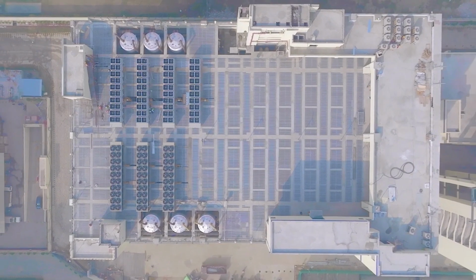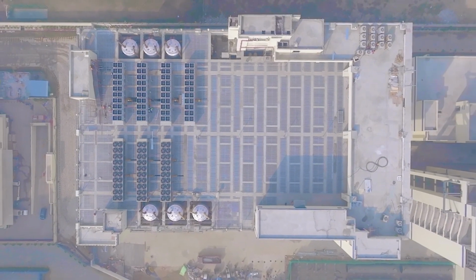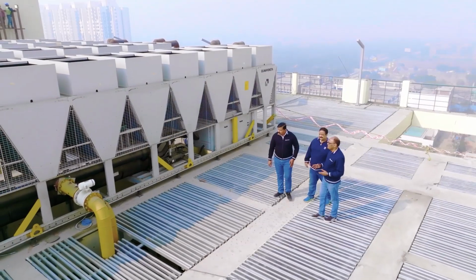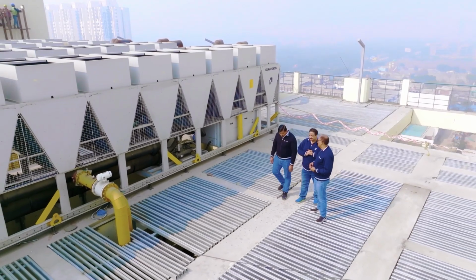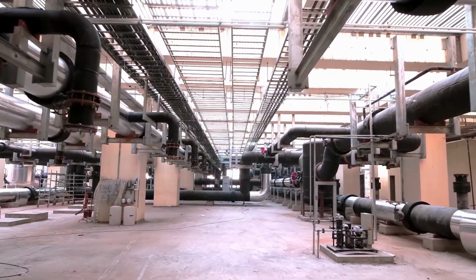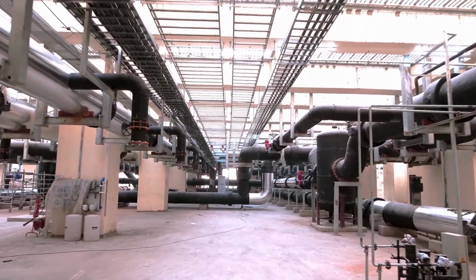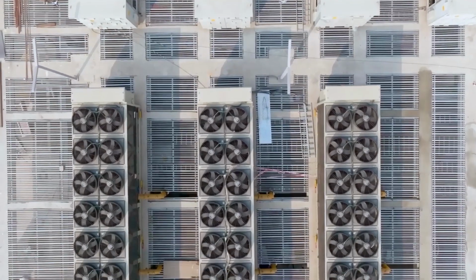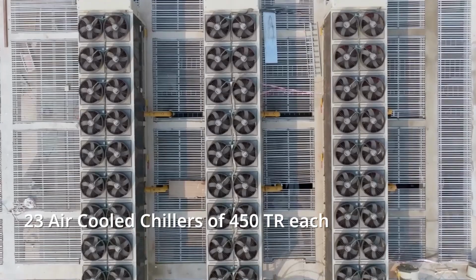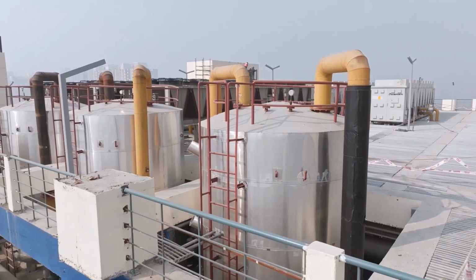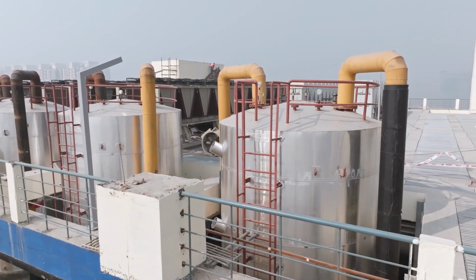We have deployed our HVAC and chiller systems here. We maintain a redundancy of N+2 for our data center HVAC systems. For sustainability purposes, we use air-cooled chillers. In total, we operate 23 units of 450TR chillers to support our IT heat load of 22.4 megawatts.